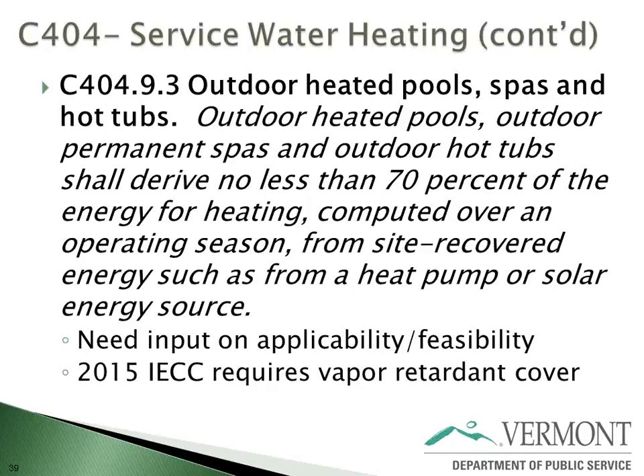It did not pass by one vote or so, and we thought, hey, we're in Vermont. We don't have a lot of outdoor heated pools, spas, and hot tubs in commercial applications, but we do have a lot of resorts, so maybe we should give this a go. What this is saying is you would have to get at least 70% of your energy for heating one of these outdoor applications from site-recovered energy, like heat recovery, or maybe a heat pump rejecting heat from somewhere else, or a renewable energy source such as solar.